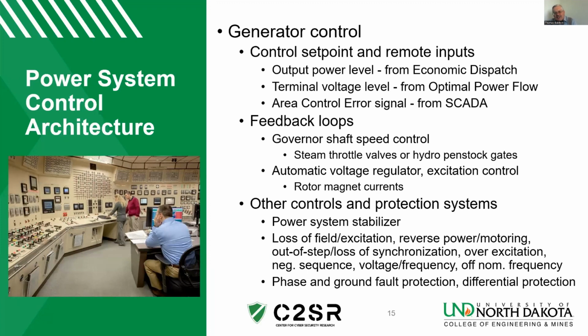Then we have protection that's built around the generator. The primary one, from a control standpoint, is the power system stabilizer. If a major event takes place and gets cleared, we're concerned that the system swings and its dynamics settle successfully. This could occur either because of a fault, or just because a large set of customers come online or shut off quickly, introducing load transients into the system and causing it to swing. Other protections are classical, such as generation protection, to make sure that the generator is operating properly, or that events just outside the power plant are also addressed if the generator has to be shut down.